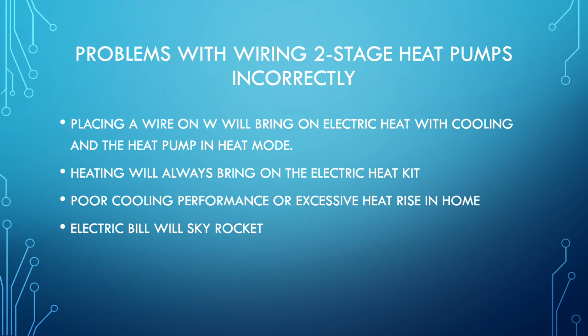So check that. Check it during heating mode when the electric heat kit should not be on and you've only increased the temperature by a couple of degrees. So heat should not have come on, depending on how you set up the thermostat. And if you do see that high amperage draw, it might tell you that you got something wrong somewhere.